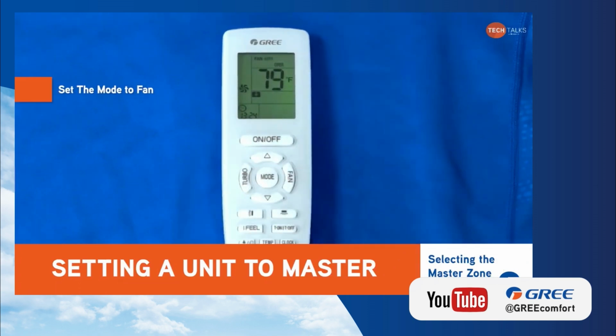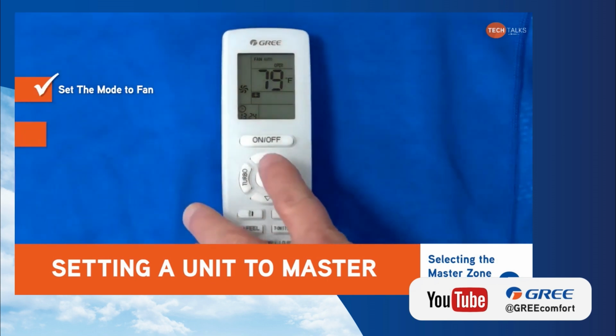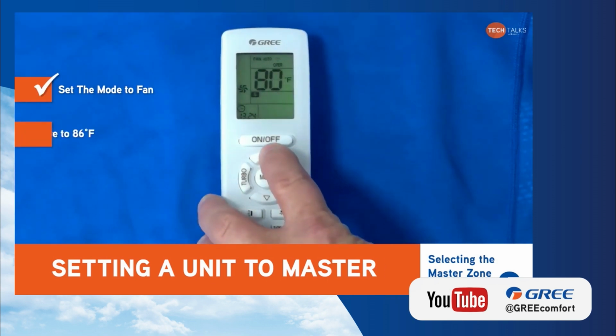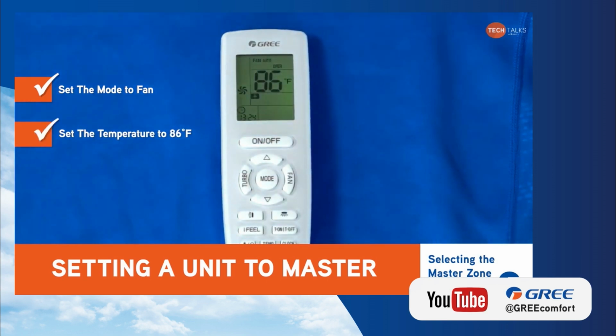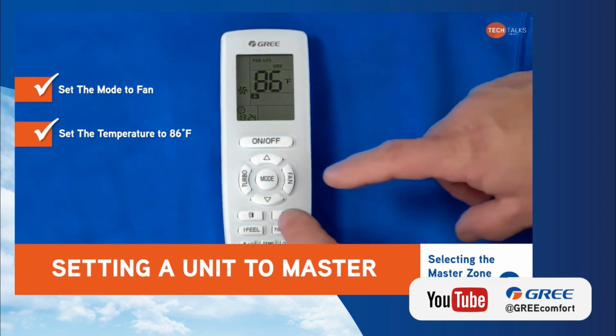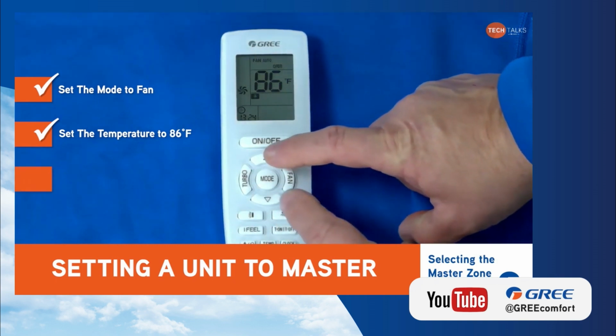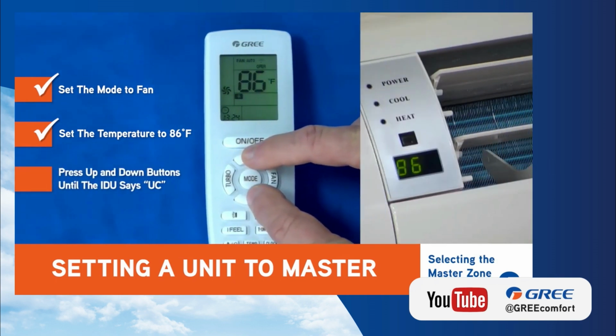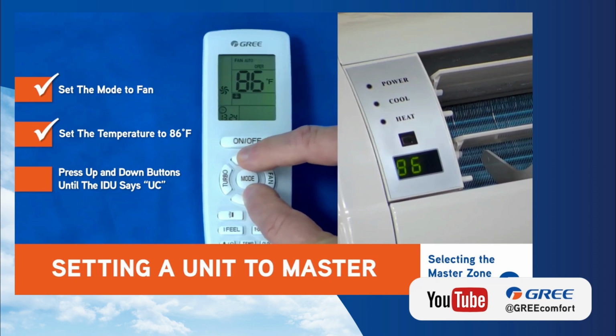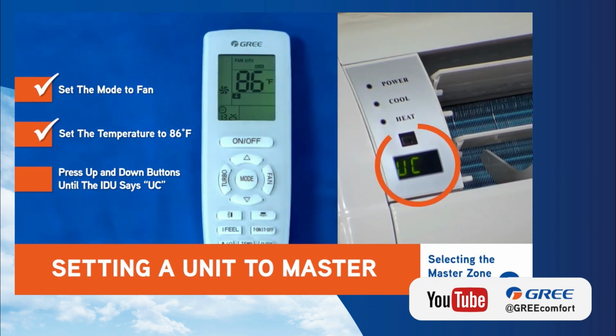So I've got the remote set to fan mode. Next, we're going to use the up key to set the temperature to 86 degrees Fahrenheit. Once it's set to 86 degrees and in fan mode, we're going to press the up and down arrow keys repeatedly, up, down, up, down, and keep doing that until you see the indoor unit say UC. Once it says UC, you've just commanded that indoor unit to be the master indoor unit.